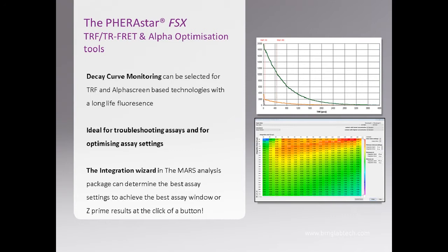When optimizing TR-FRET assays, especially in-house built technology assays, the system can also perform decay curve monitoring. This allows us to see the true decay and can be useful for troubleshooting. With time-resolved fluorescence assays, we need to determine the point at which we start collecting the light and how long we collect it for. Using this feature for optimization, we have a built-in integration wizard in our analysis software that, by choosing whether you want to gauge measurements against Z-prime or signal window, can give you an idea of all the permutations and the best settings for your assay configuration — very useful in optimizing signal window and Z-prime for these assays.